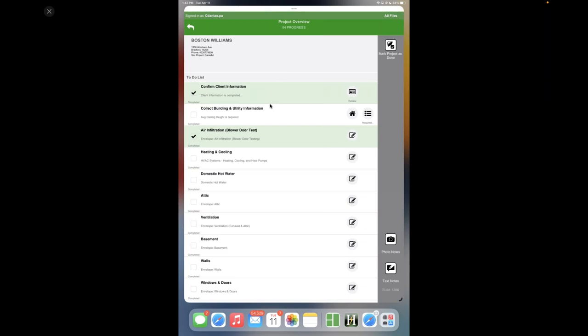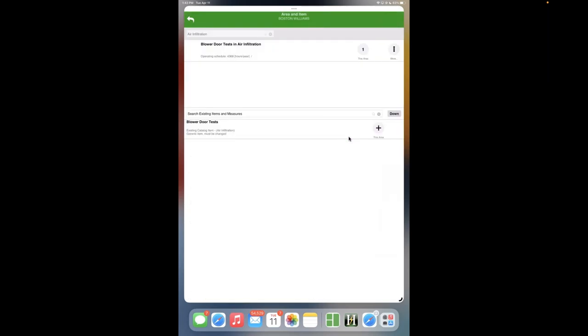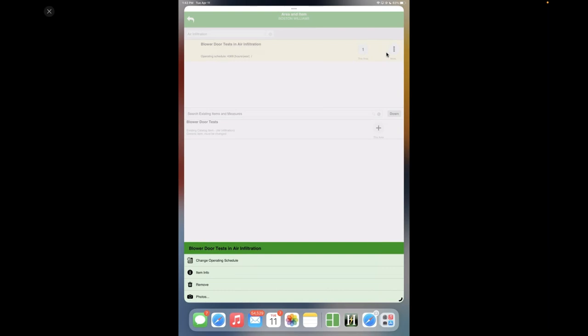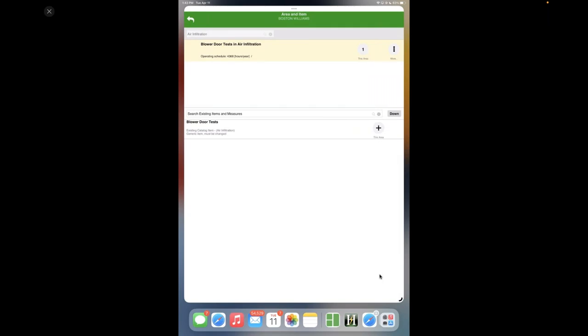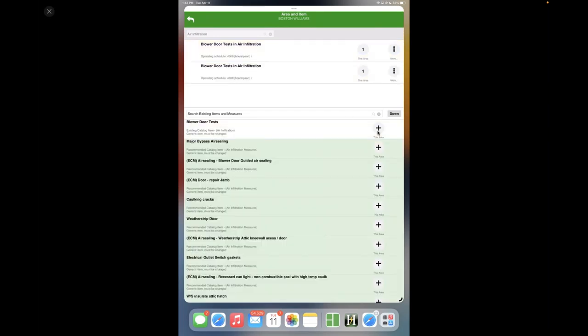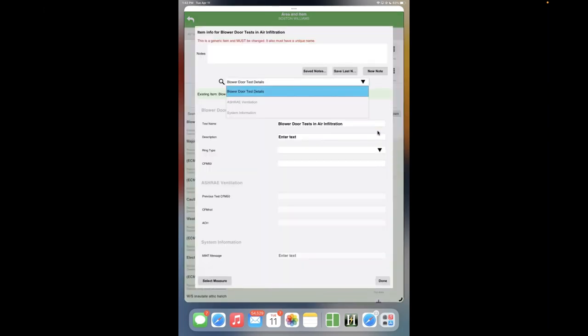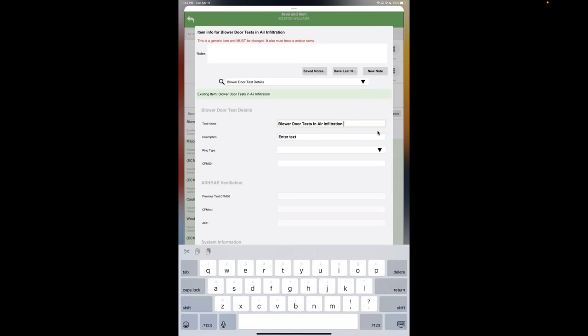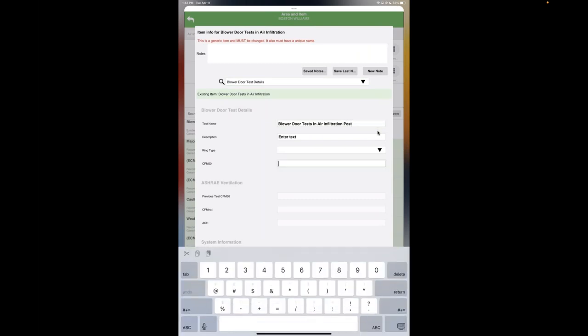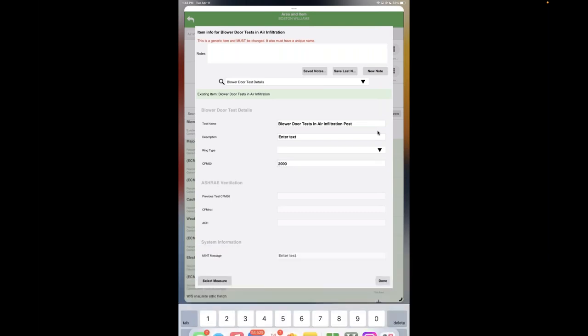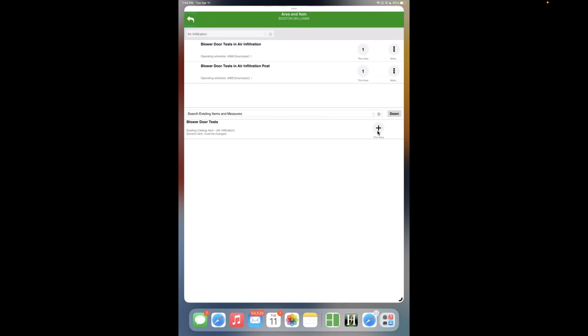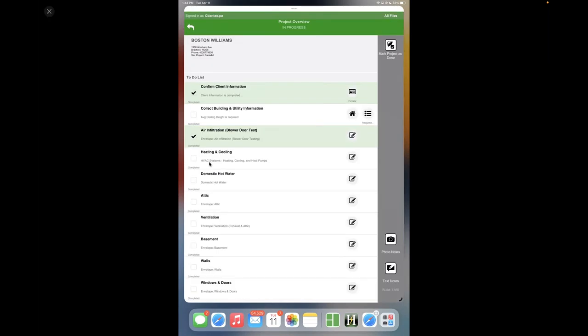So then you get the sense that this to-do list, after you enter and confirm the utility information, then you can go and start your step-by-step BPI guided audit. So we're going to look at a blower door test. I have already entered a pre-test here, just to save time. And that pre-test has a CFM at 3000. When I enter multiple tests as I'm weatherizing, as I'm installing the measures, you can enter as many tests as you want. And you do that simply by adding a new test. Let's say we're at the post-test and then you can enter the CFM50. So let's say we got to a 1400 CFM reduction.